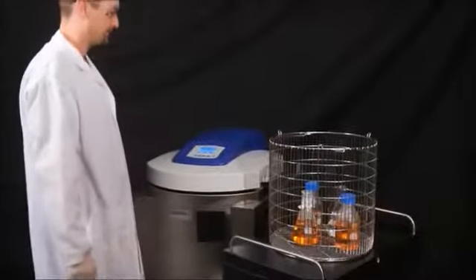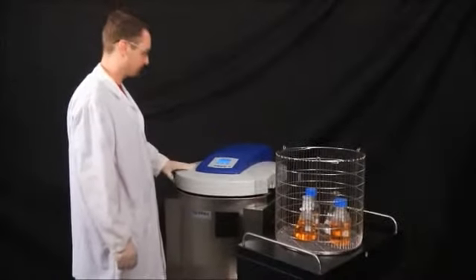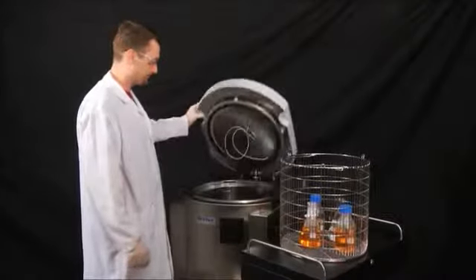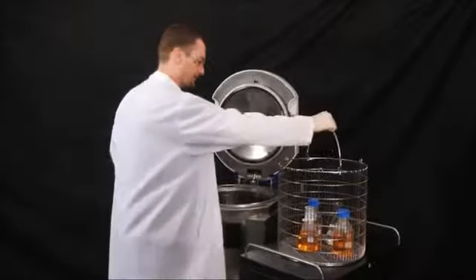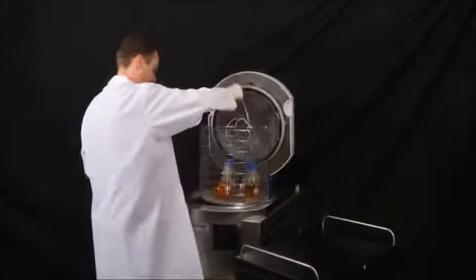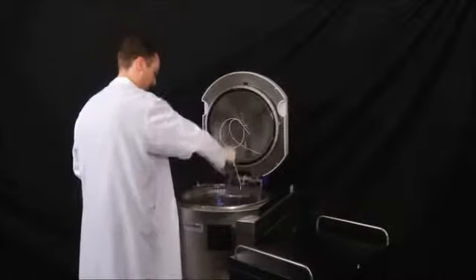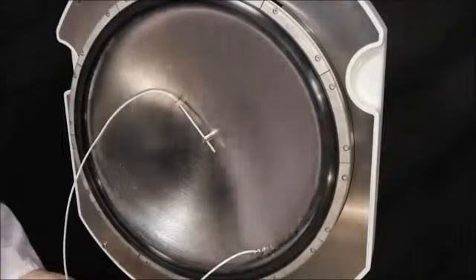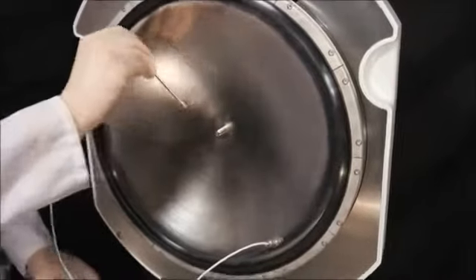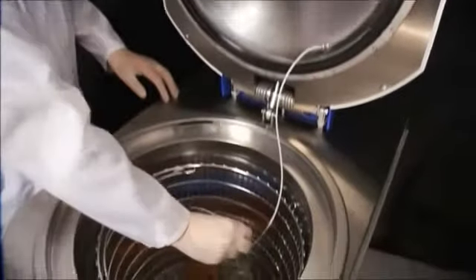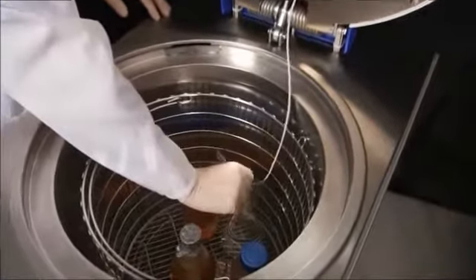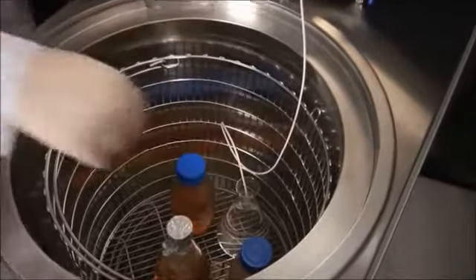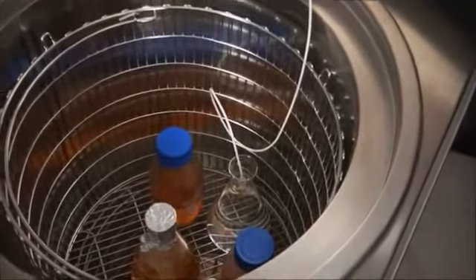Accurate liquid sterilization is one of the most challenging tasks in the laboratory. Conventional autoclaves do not have the capability to measure liquids being sterilized. Often liquids boil over, are over-sterilized, or not sterilized at all. All Systec autoclaves include a flexible PT100 temperature probe. This probe directly measures temperature of the liquid being sterilized, ensuring accurate and precise control throughout the entire sterilization process.